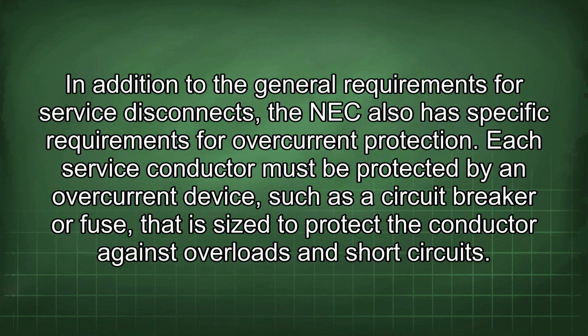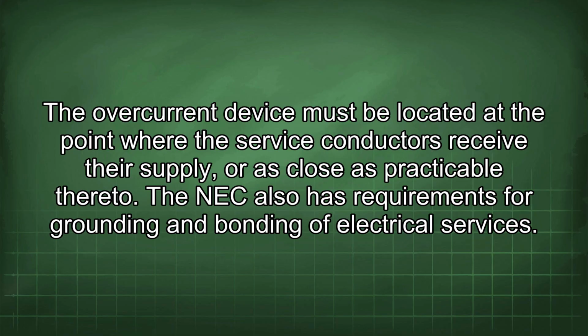In addition to the general requirements for service disconnects, the NEC also has specific requirements for overcurrent protection. Each service conductor must be protected by an overcurrent device, such as a circuit breaker or fuse, that is sized to protect the conductor against overloads and short circuits. The overcurrent device must be located at the point where the service conductors receive their supply, or as close as practicable thereto. The NEC also has requirements for grounding and bonding of electrical services.